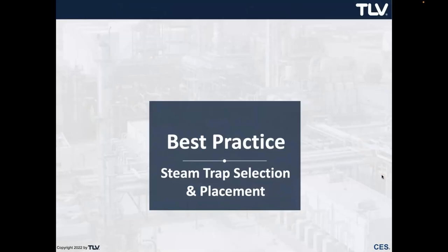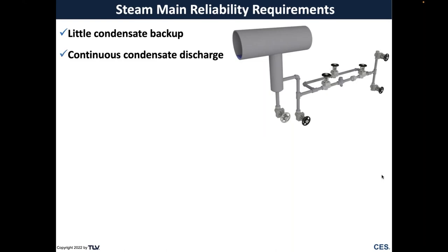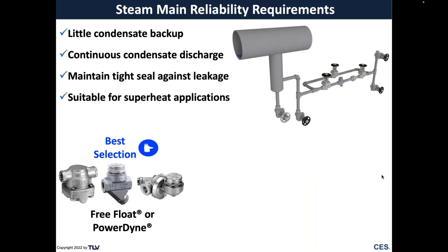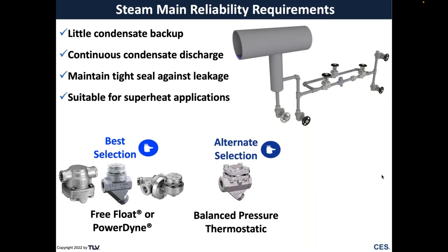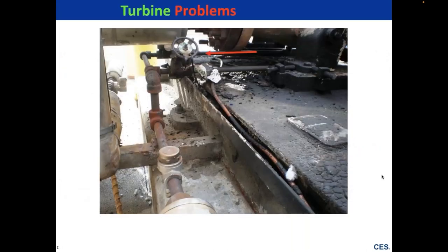Steam main reliability requirements: we want little condensate backup, achieve continuous discharge, maintain a tight seal against steam leakage, and suitability for superheat applications where appropriate. Let your trap vendor make the best selection. Even with TLV models, we have alternate selections — for example, we make a very powerful bimetallic trap, but we would never use that for steam mains; it's used for different applications.